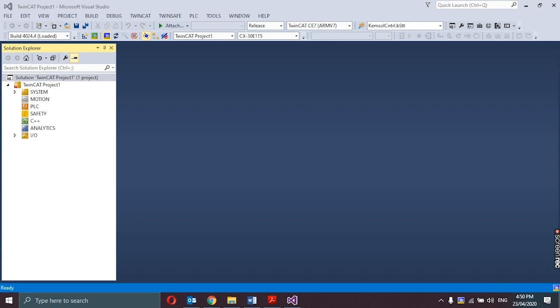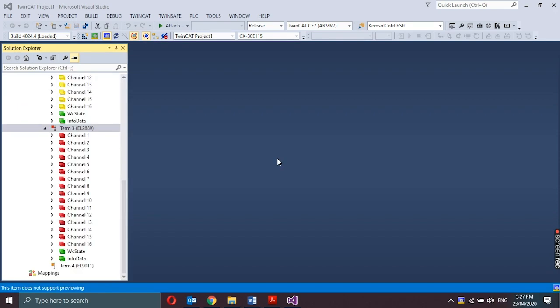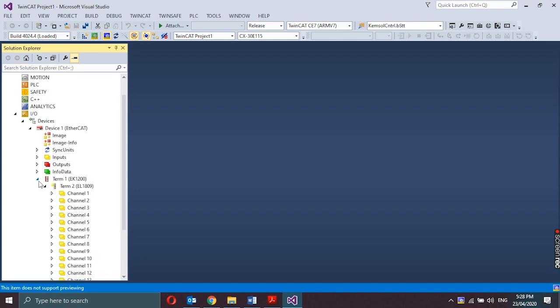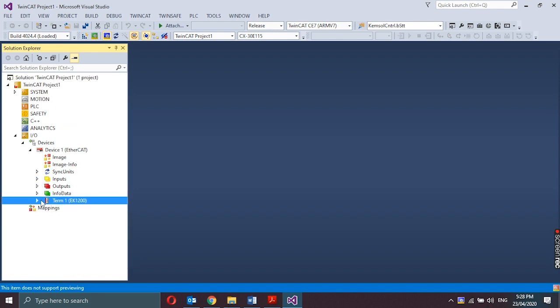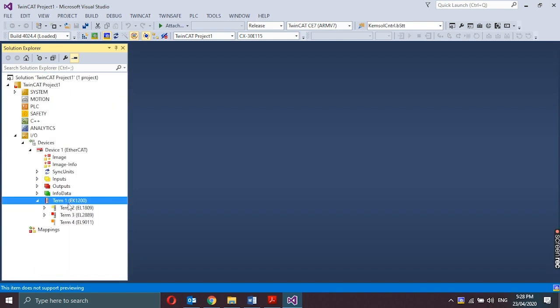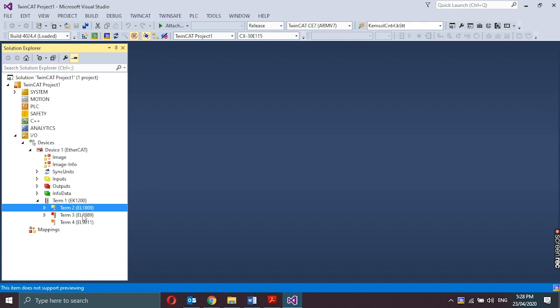Note the differentiation between TwinCAT programming system and the TwinCAT target system. The TwinCAT icon next to the Windows clock always shows the TwinCAT mode of the local PC. The system manager windows shows the TwinCAT state of the target system. We could also see that the scanned I.O. terminals are arranged based on the actual hardware setup. The first one is the 16-channel digital input and the second one is the 16-channel digital output as arranged in the actual setup.